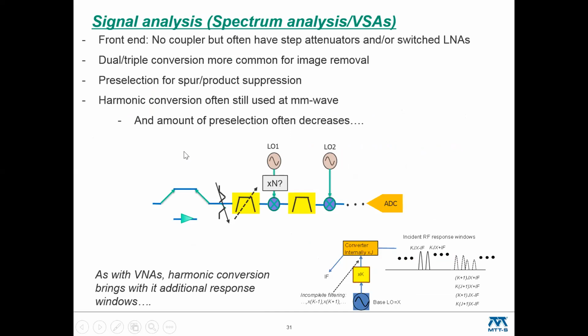Well, shifting more officially now into signal analysis, what is different architecturally? And historically, there was quite a lot, and certainly at lower frequencies there still is, where there's usually more conversion stages to reduce spurious content. You really are looking for an unknown signal, typically. There was pre-selection, some variable filtering up front, again, for spur removal and for linearity assistance and some other reasons. There may have been some of the variable gain we talked about earlier, and that's certainly true.